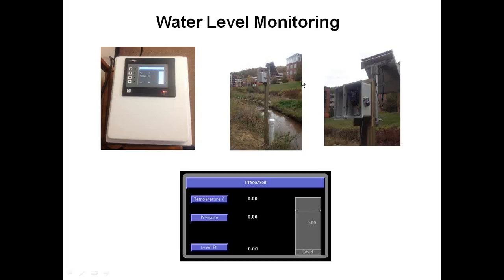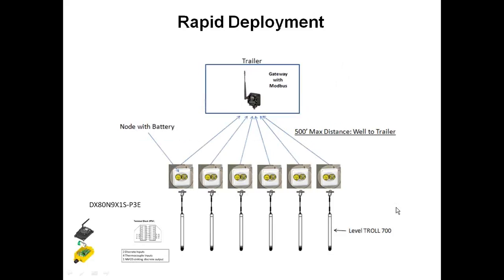Here's another outdoor level monitoring setup where we used one of our solar panels. We have a 4 to 20 transducer in the water, coming up to the node with the battery. We added the solar panel because they wanted to run in Modbus mode, which pulls more power than the 4 to 20 signal. This is picked up here, and back in the administrative area they have an HMI reporting temperature, pressure, level, and a bar graph of the level.